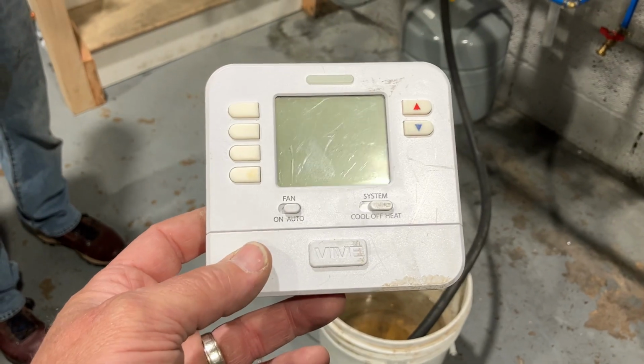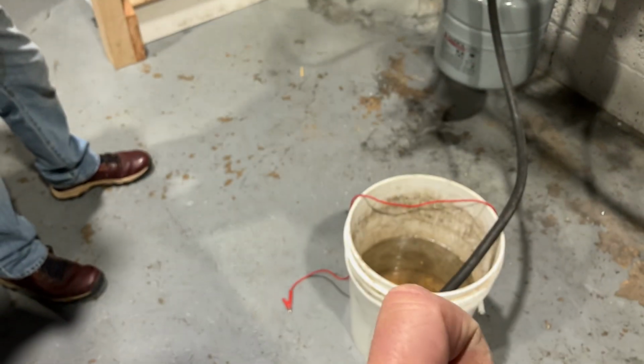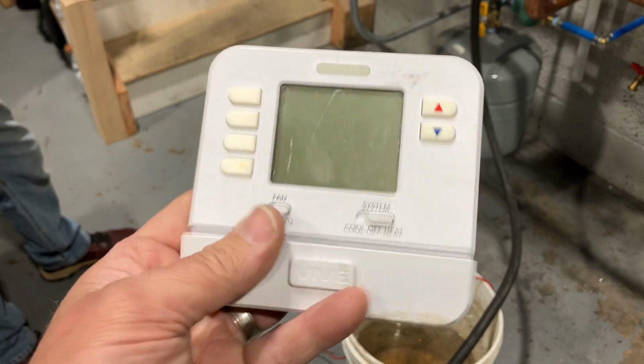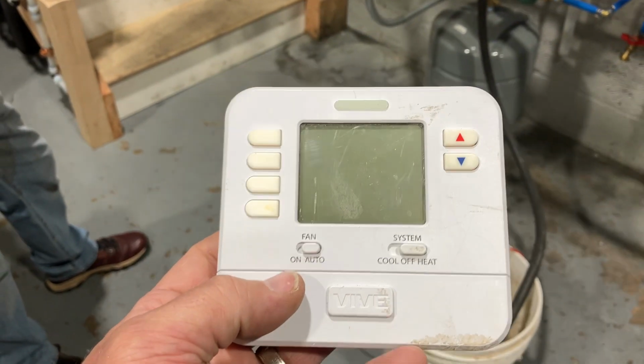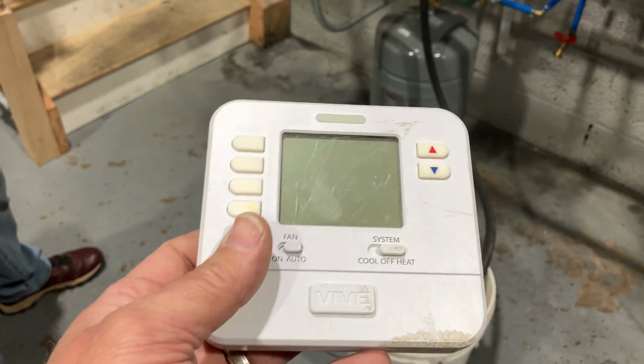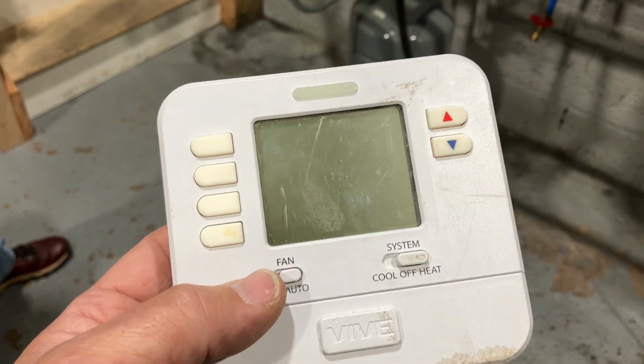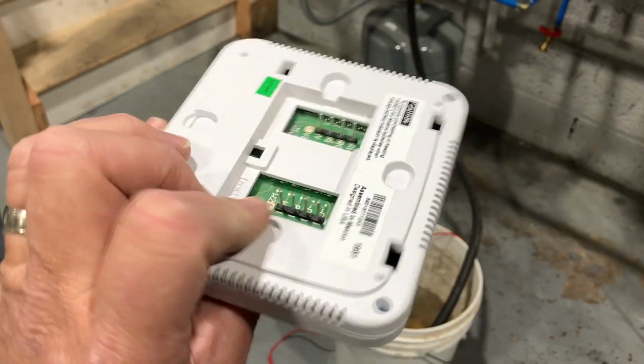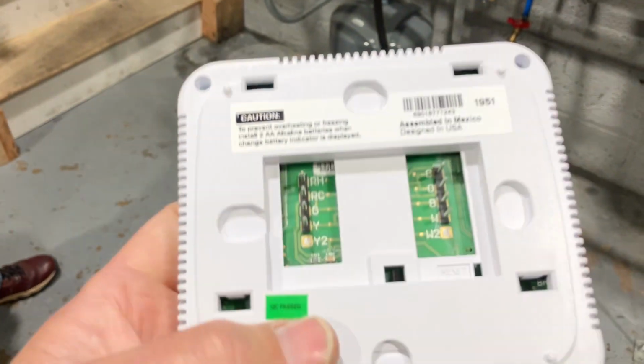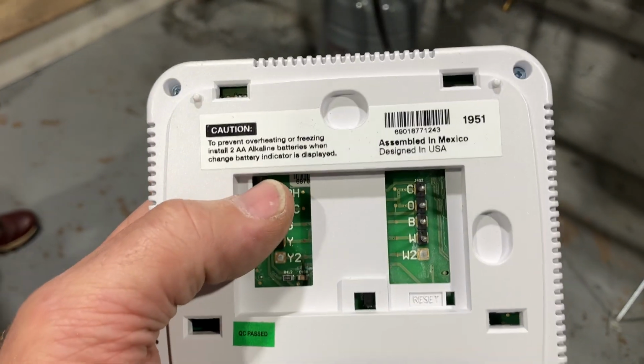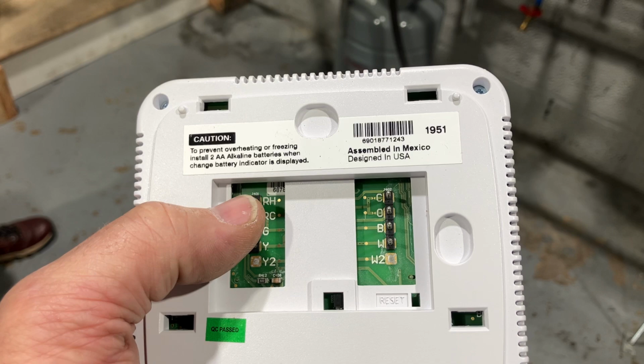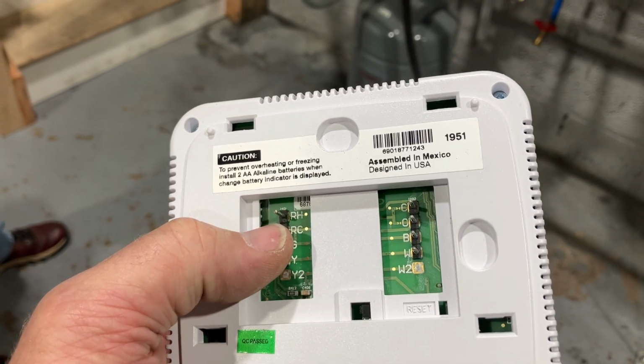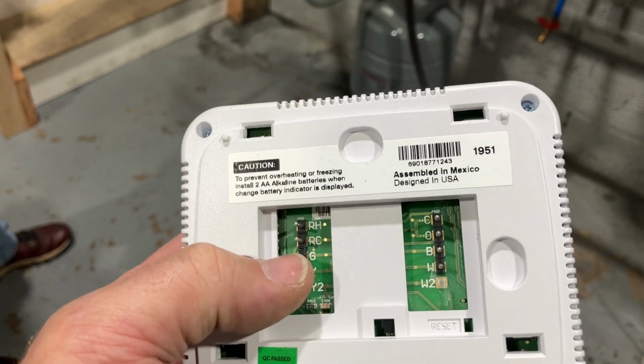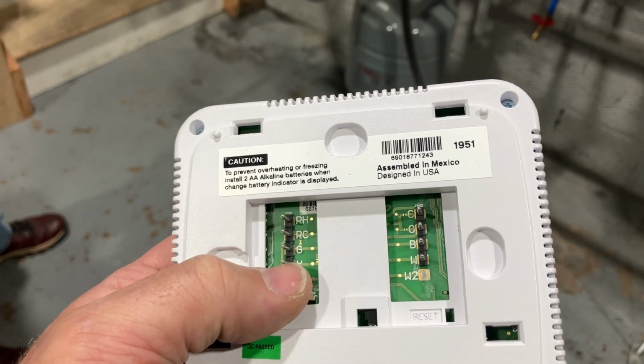All right, ladies and gentlemen, we're going to start with a traditional battery-operated single-stage cooling and heating thermostat. Nothing fancy, not touchscreen, not Wi-Fi, just a digital display that runs on batteries. We have multiple terminals in the back of the thermostat: RC and RH, for your relay for heating, relay for cooling. There's your 24 volts. G for fan, Y for cooling.